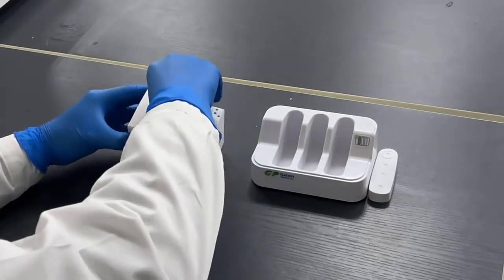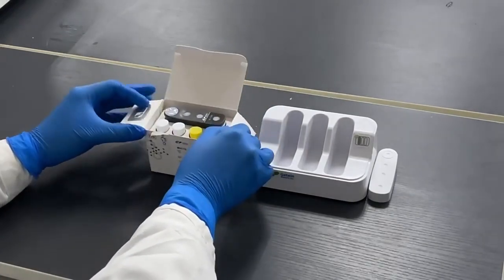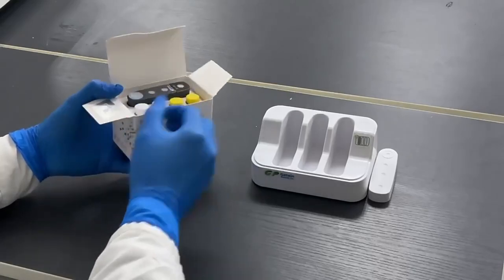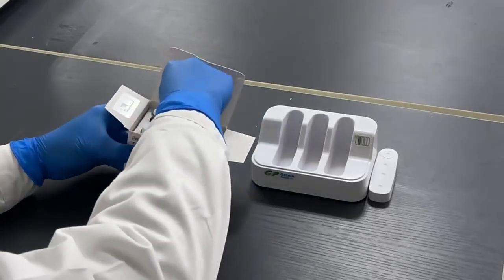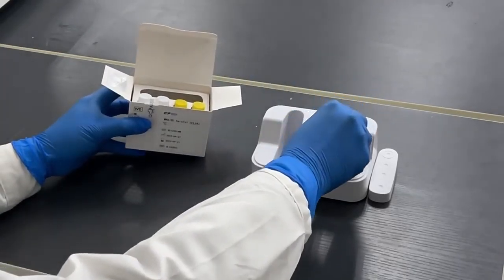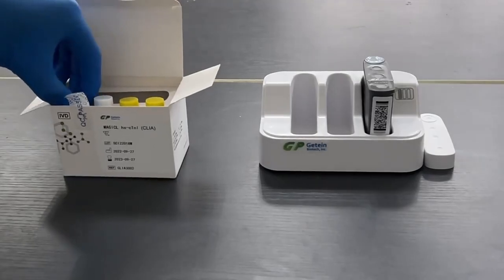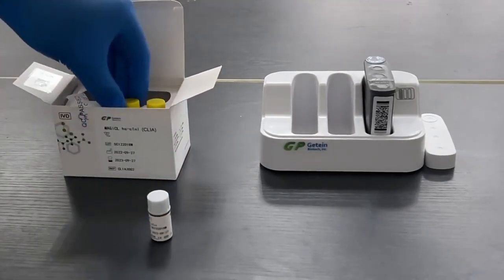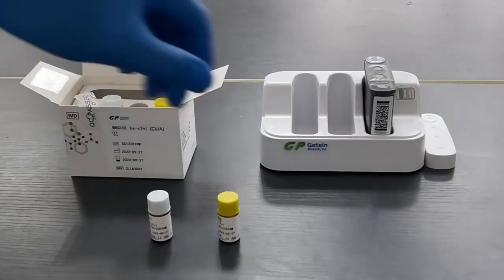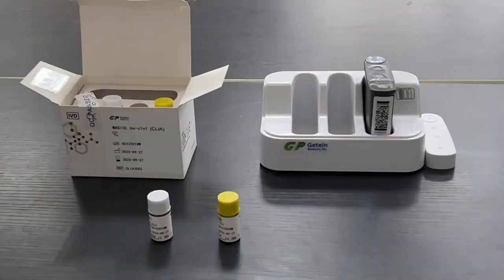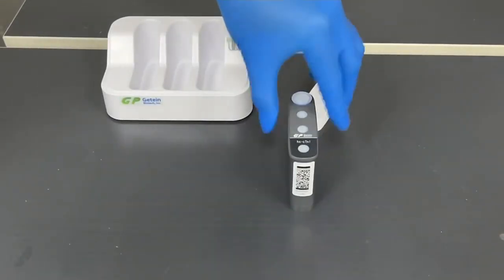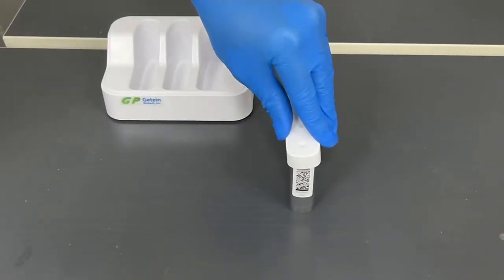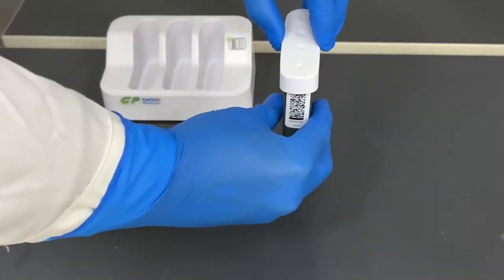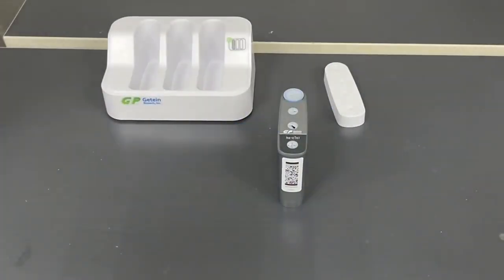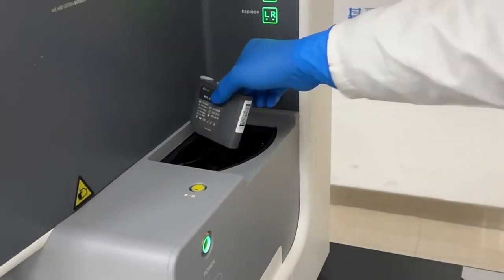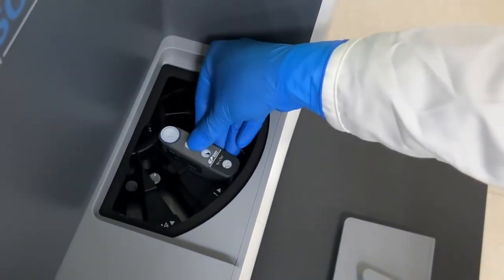Reagent preparation. Open the kit. Take out the reagent and the high and low concentration calibrators. Leave the reagent on the magnetics premixing tool for a few minutes. Use the piercing tool to open the reagents. Uncover the reagent tray on the right side of the machine, insert the reagents and close the tray.